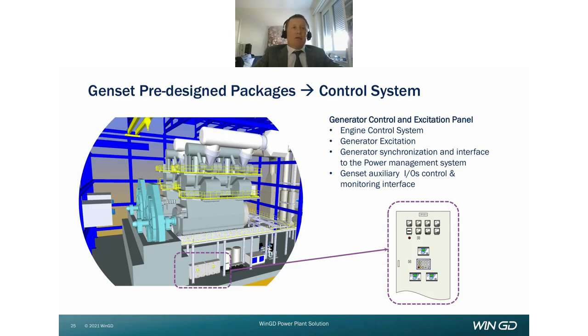The PMS determines which genset of the power plant fleet must be online and its respective power set point based on several factors like the consumer demand, the amount of spinning reserve, and the redundancy needed. The GCP can be set in local mode in order to carry out the genset maintenance or troubleshooting without disturbing the plant operation. The GCP is designed to be remotely monitored by WinGD for predictive maintenance and remote diagnostics.